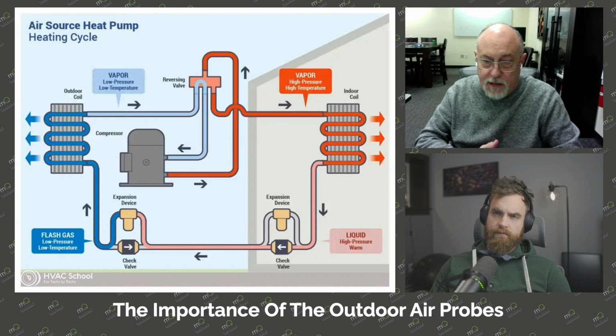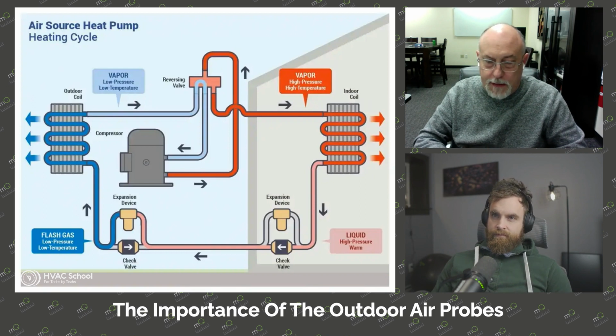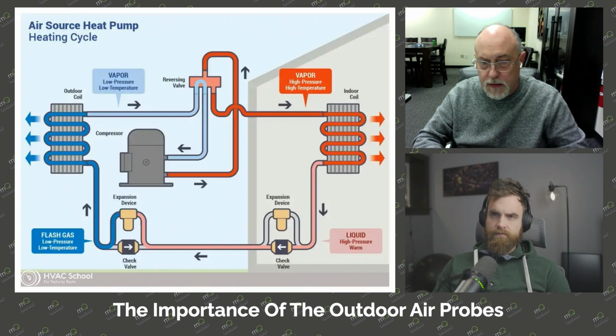Outdoor air temperature, we need to get outdoors. That is like the most important probe on a heat pump. That's the driver for everything. We're going to put that outdoor air probe about midway on the coil, out of line of the sun. We don't want the sun shining on it, because we want to get a true outdoor air temperature. What's the outdoor air temperature entering that heat pump? Because that's going to really determine how much heat we have to work with. And then we're going to measure indoors. We're going to measure total external static pressure, and we're going to measure supply air temperature and return air temperature, just like we would on an air conditioning system.